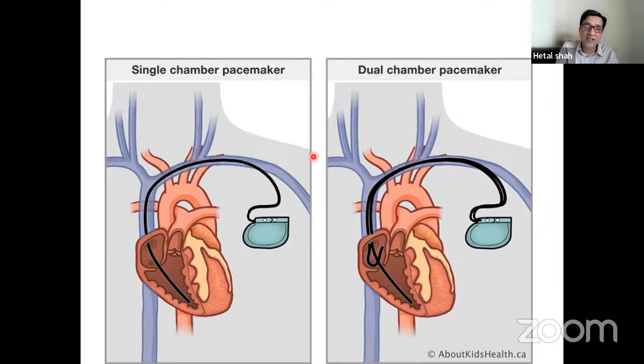So you have to understand the coding. If you understand the coding of the pacemaker, you will understand what kind of pacemaker the patient has. So the first letter, as I said, VOO or DOO or AOO. What does that first letter mean? The first letter means the chamber which is going to be paced. That chamber is the chamber which is going to be paced by the pacemaker.